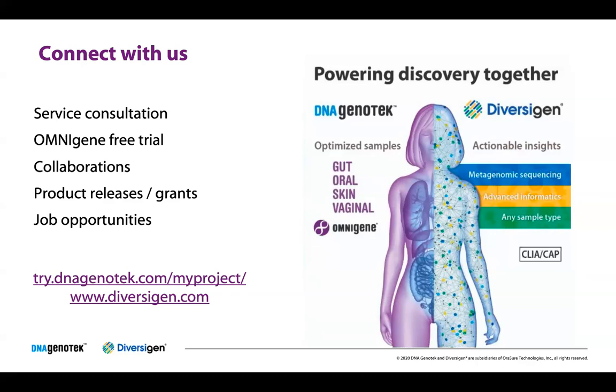Can this be used for fecal samples taken from rats? I'm not in a position to say if that's been tested and validated. By far, the impact of this device is for humans — it's really designed for human hands to add the sample in and homogenize it. That's where a lot of the research is going. Seven days for shipping is perhaps extreme — how much variation at T1 and T2? We did see that there was a change after one and two days, but it was a gradual and consistent change with the cooler. After about two days, the cooler reached room temperature, so at that point the sample had no longer had any cooling preservation.